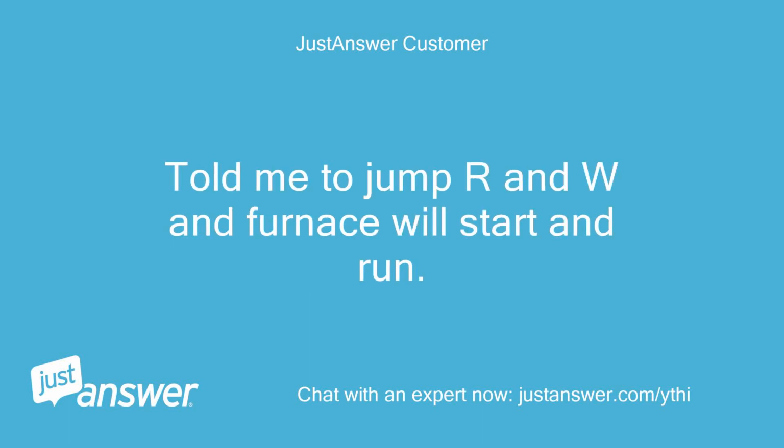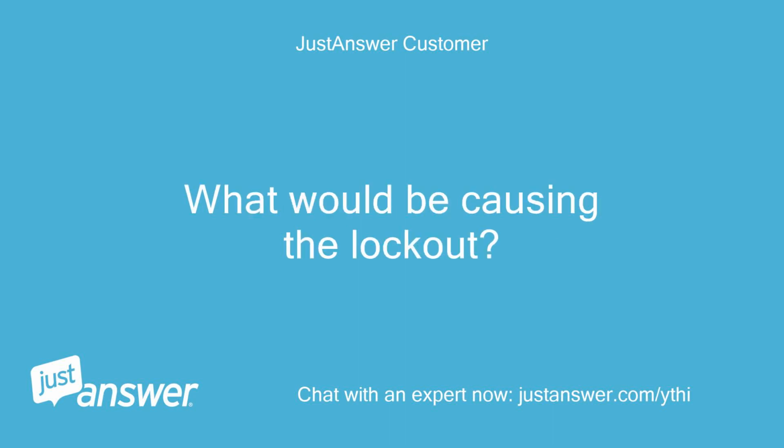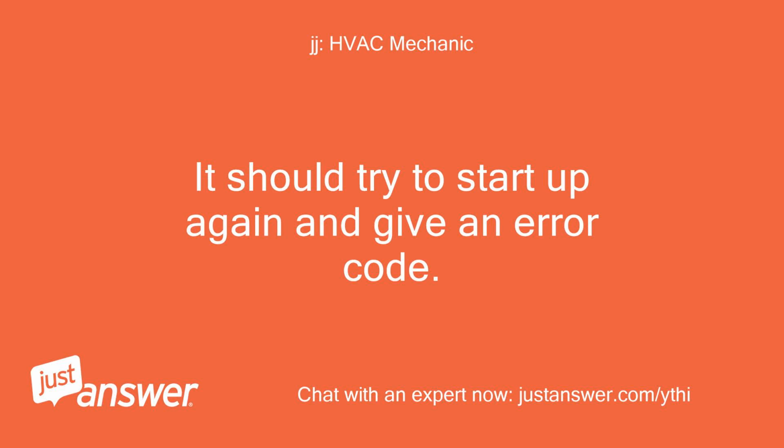Told me to jump R and W and the furnace will start and run. Well, it is still in lockout. What would be causing the lockout? Blower just keeps running. It should come out of lockout when you reapply power. It should try to start up again and give an error code.